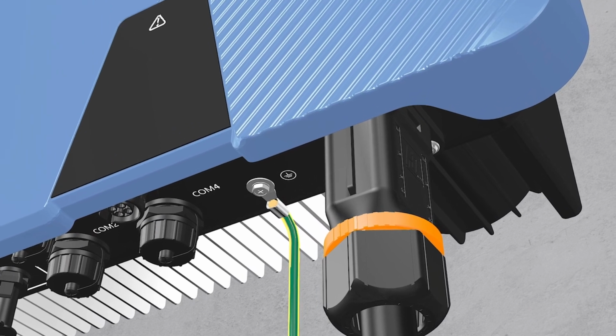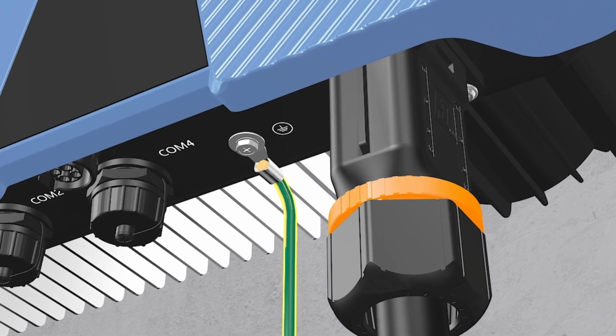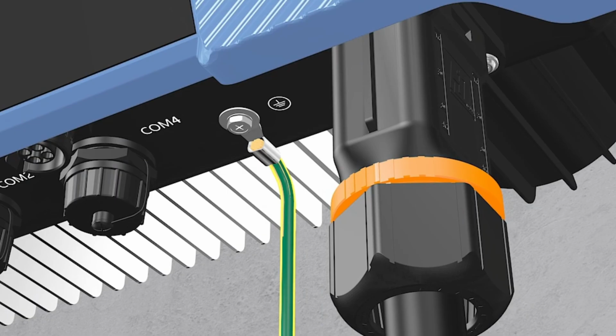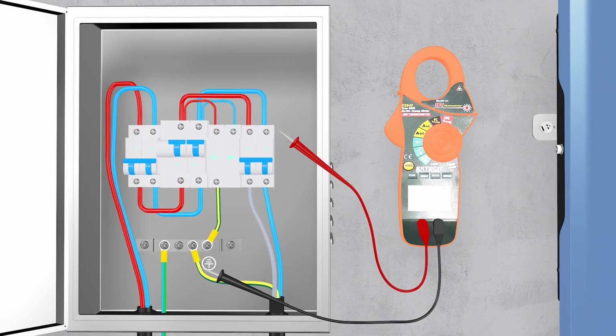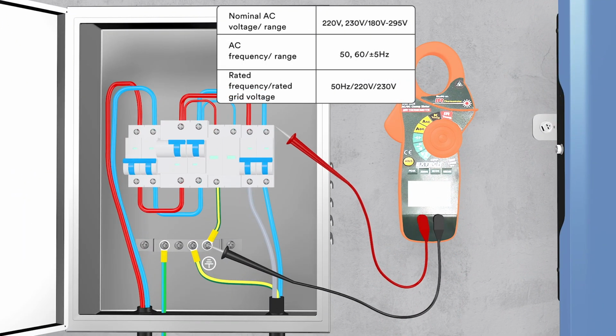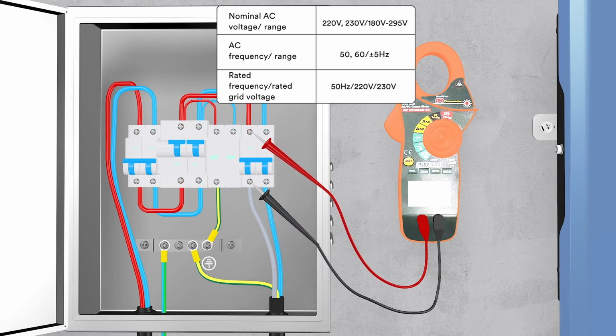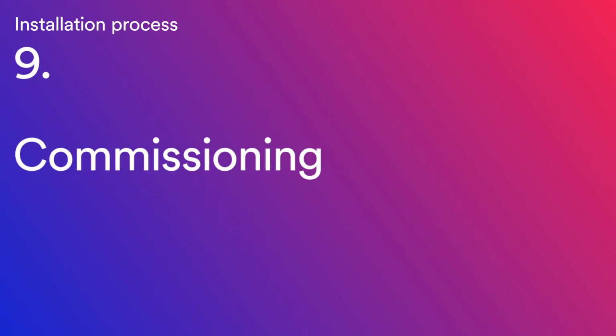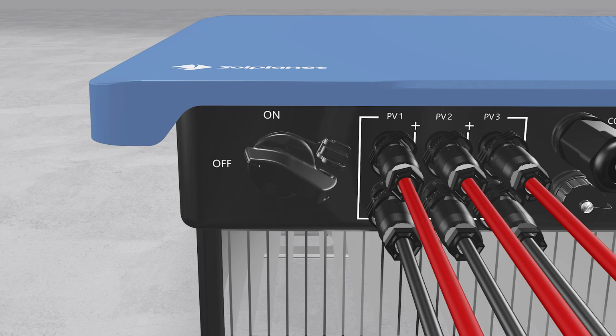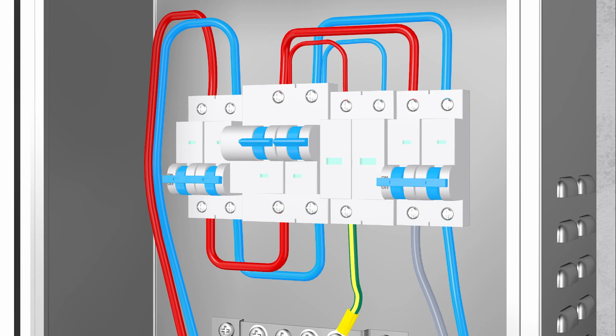Check the PE connection with a multimeter. Make sure that the inverter's exposed metal surface has a ground connection. Check the grid voltage. Check that the grid voltage at the point of connection of the inverter complies with the permitted value. Switch on the miniature circuit breaker and DC switch.